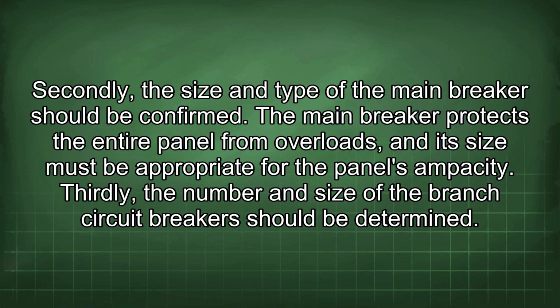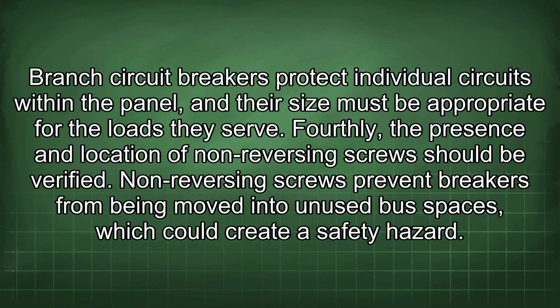Thirdly, the number and size of the branch circuit breakers should be determined. Branch circuit breakers protect individual circuits within the panel, and their size must be appropriate for the loads they serve. Fourthly, the presence and location of non-reversing screws should be verified. Non-reversing screws prevent breakers from being moved into unused bus spaces, which could create a safety hazard.